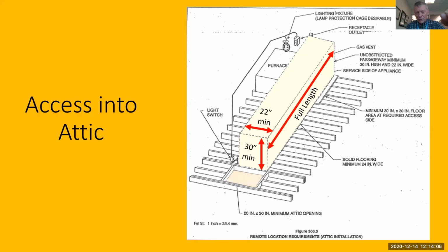So when you're running your duct work on new construction, or if it's a retrofit and maybe you add duct work and have to cross over, that's going to limit your length of how far you can place that appliance at that point. If all you're going to have is a 30-inch height, you've just restricted yourself. That will stay at the 20-foot maximum from the scuttle opening.